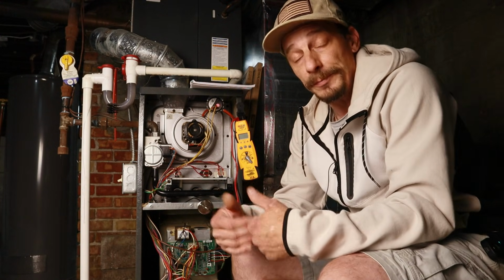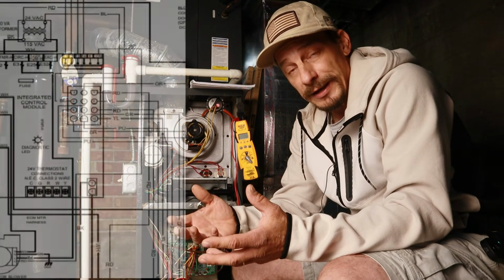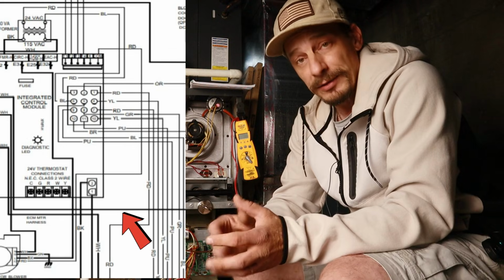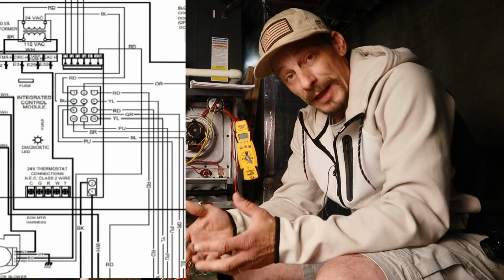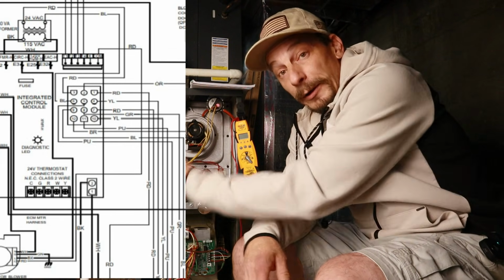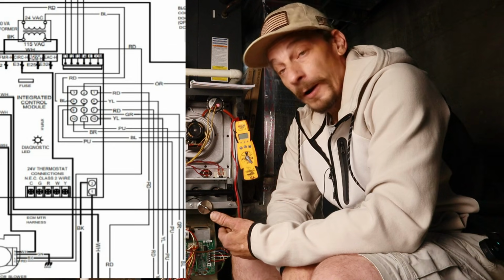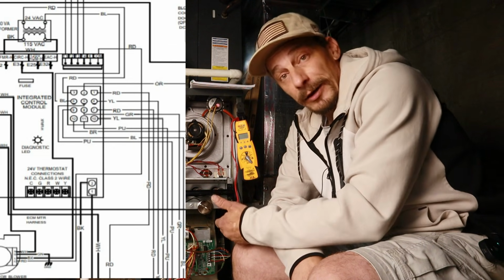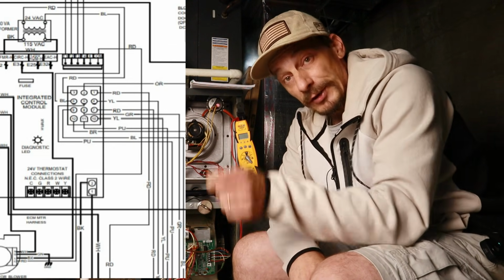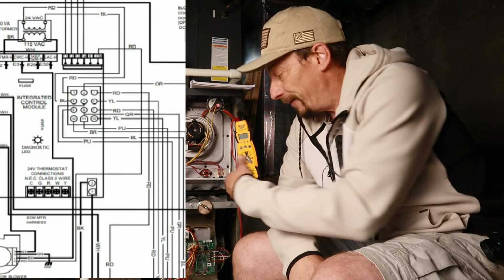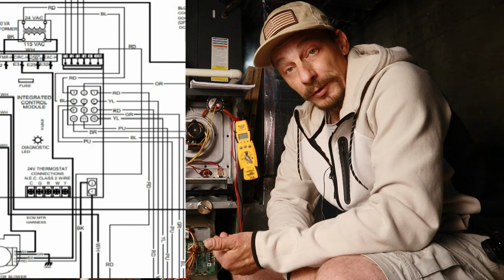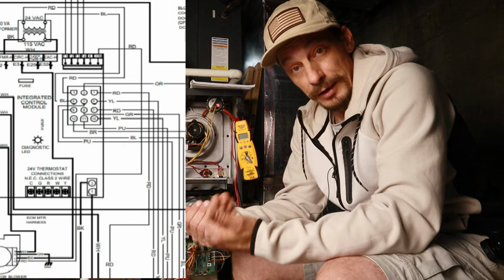Now, if we back up a little bit, we take a quick look at this diagram again, you'll notice that there's thick black lines and thin black lines. The thick black lines were high voltage, and that's what we were testing through most of this video so far. But once we got on the secondary side of the transformer, you notice the lines on the diagram, they got thin, and from that point on, we were testing low voltage, so we were getting 24 volts on those wires.